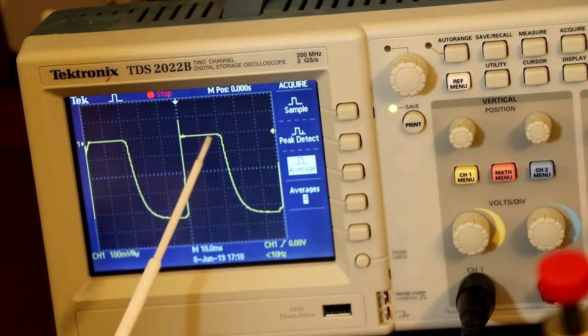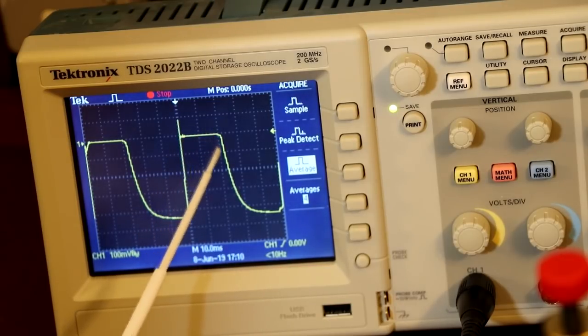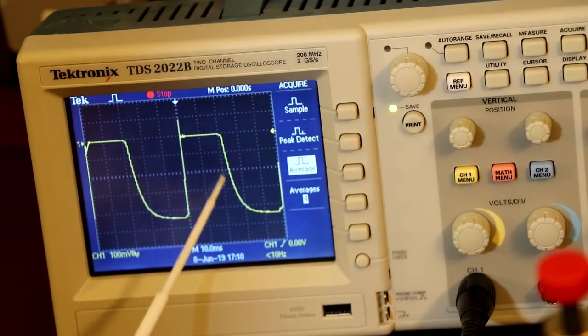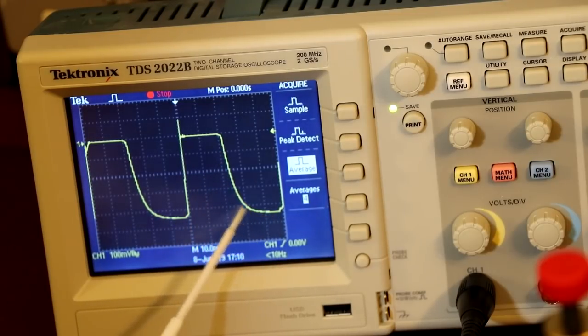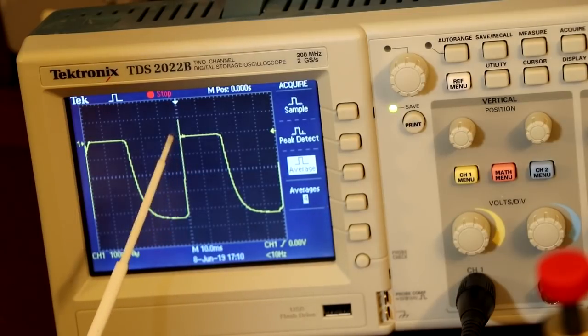But I think what's more interesting is if you look at where the coil switches off, you can see this curve here at the bottom. It's a sharp edge, but it's a curve, and that shows us the capacitor doing its job. Effectively, when we switch the power onto the coil, the capacitor is switched out of circuit, so it doesn't do anything to limit the rise time.